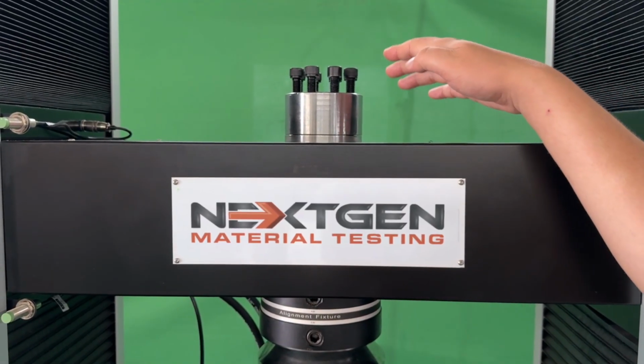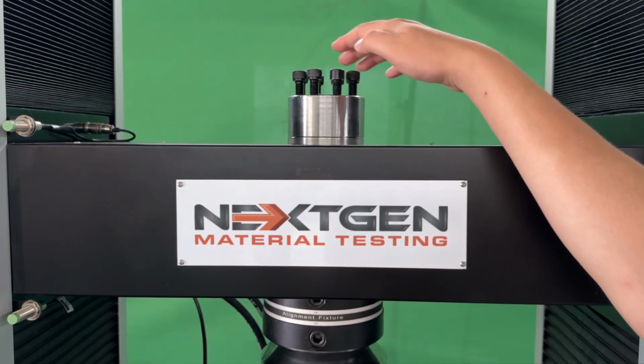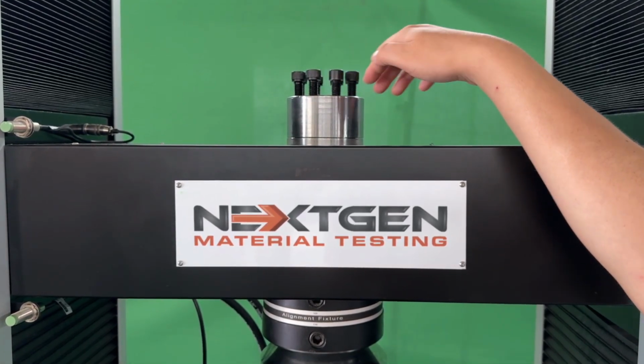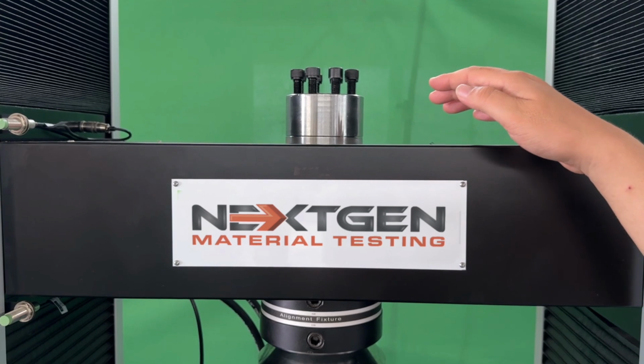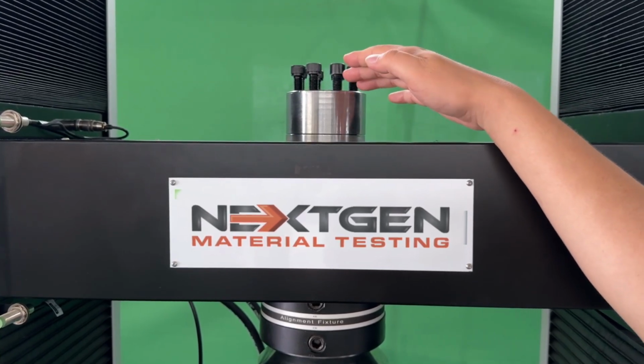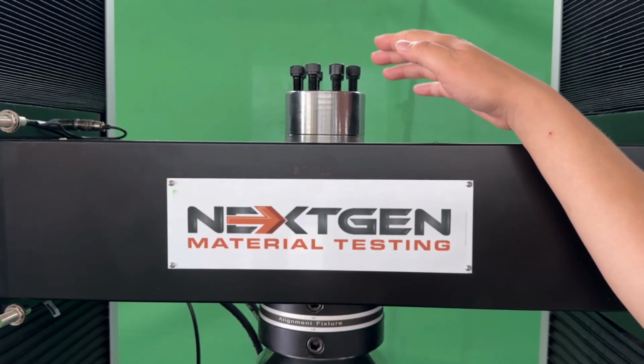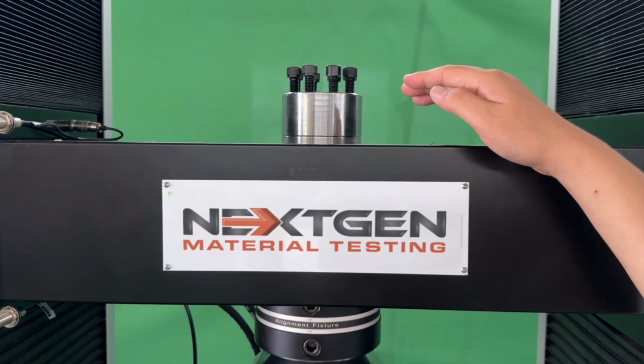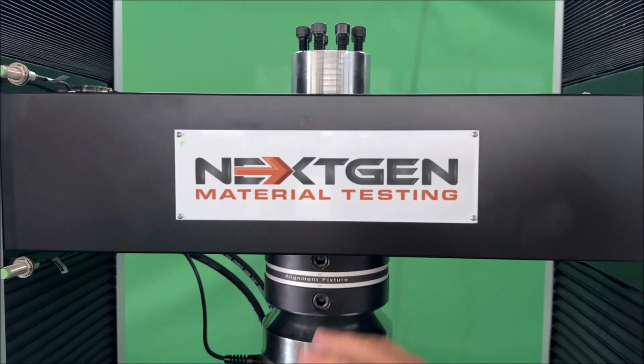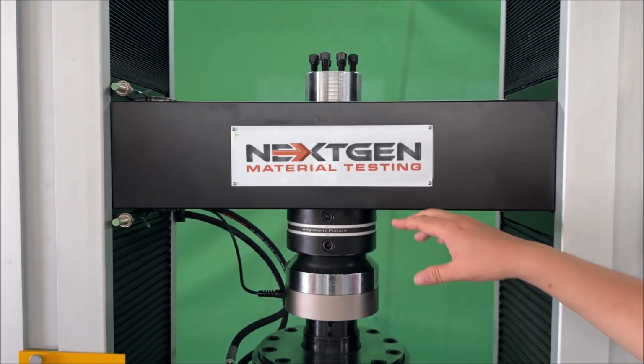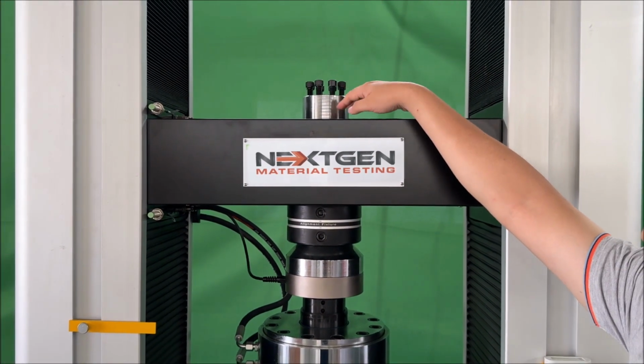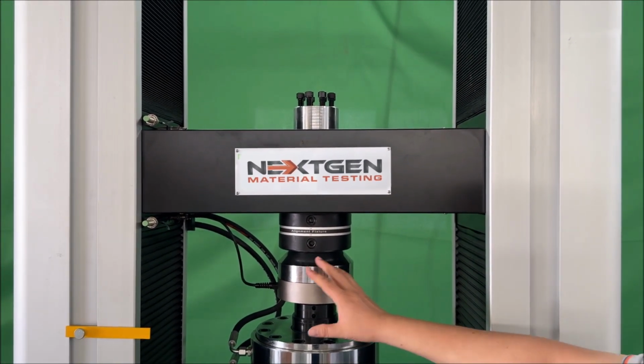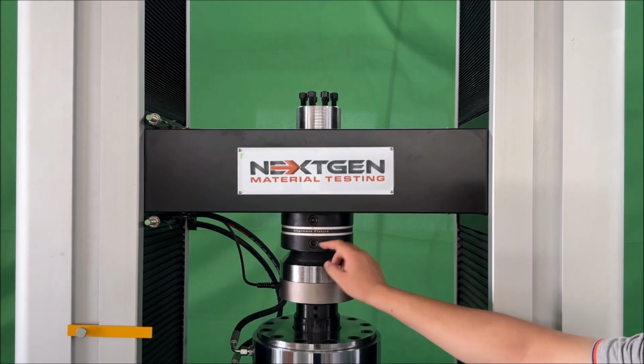Before dispatch, the bolts at the top were firmly tightened to maintain proper machine alignment. Do not unscrew these bolts, as doing so will cause misalignment and prevent the machine from passing NADCAP certification. For alignment adjustments, use the bolts on the alignment device directly.